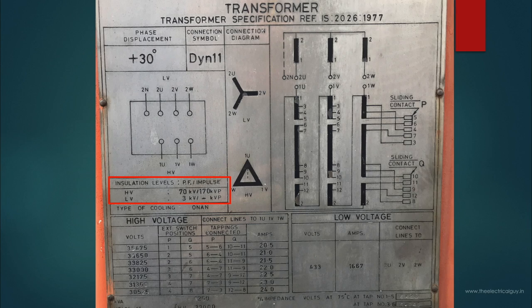This insulation level also consists of switching impulse voltage which is generally applicable above 245kV only. This is a nameplate of 33kV and hence it is not applicable for this particular transformer. Let's understand why these insulation levels are important.